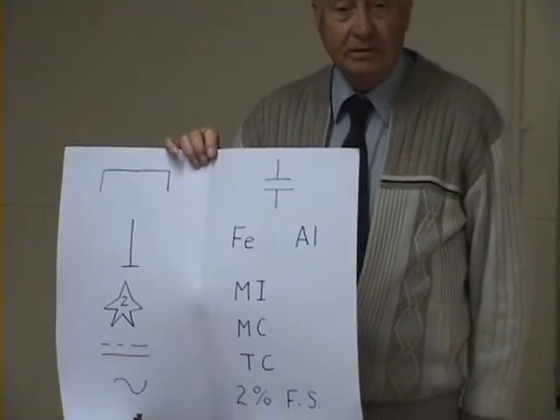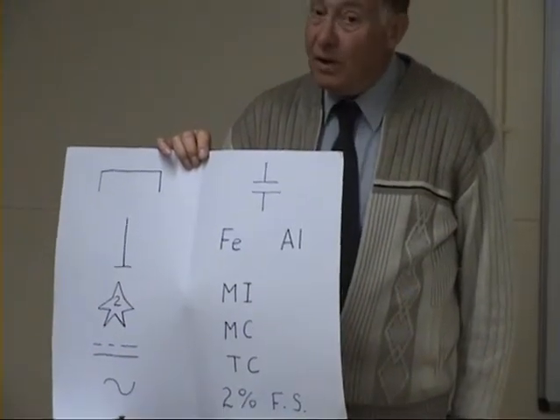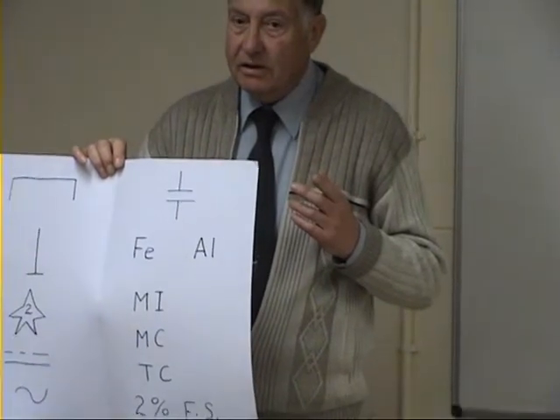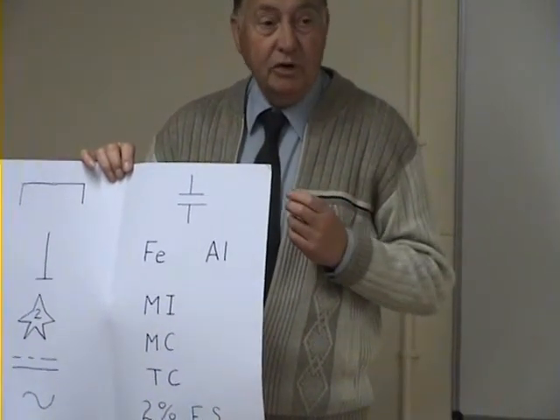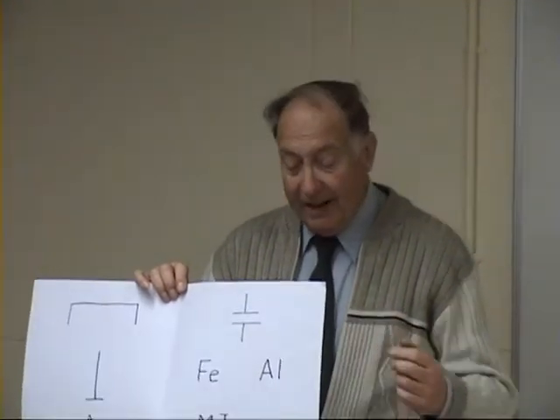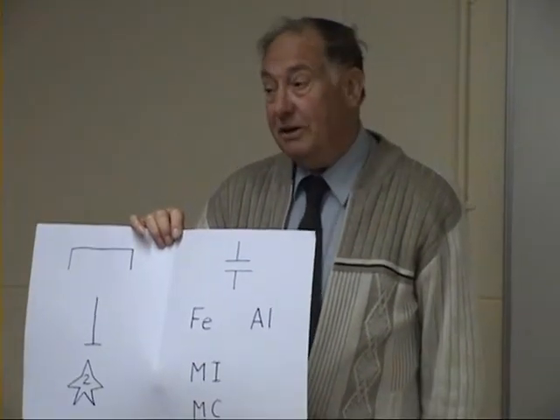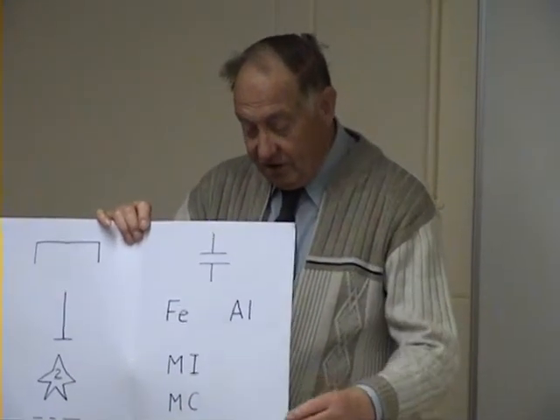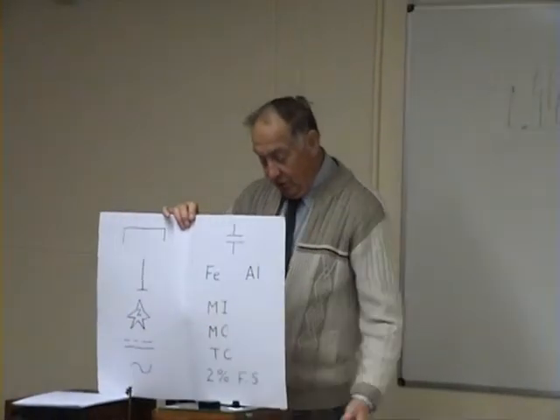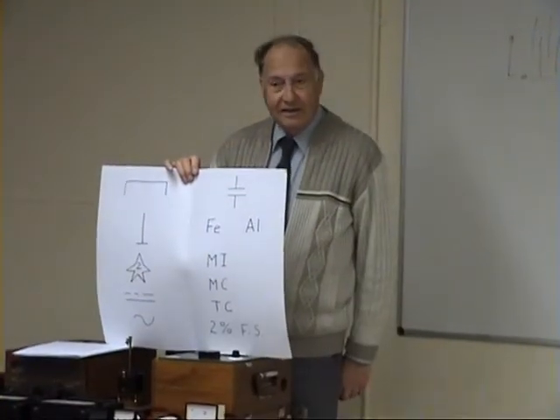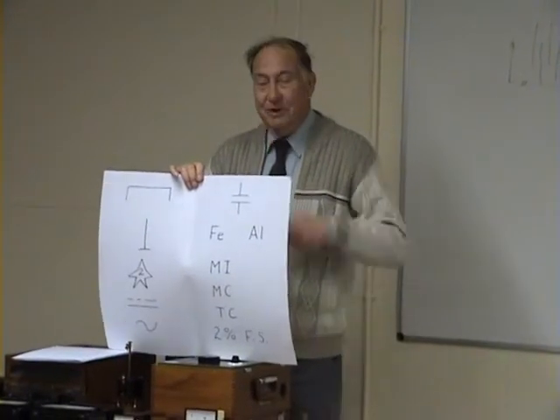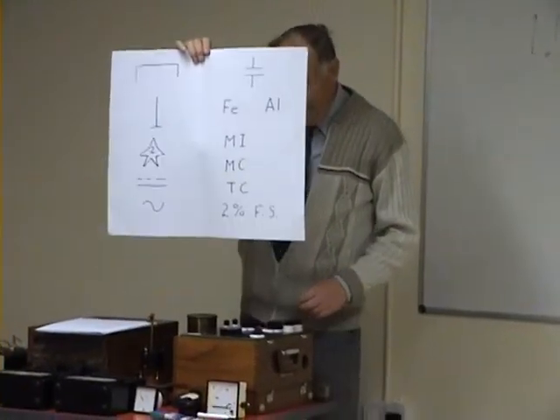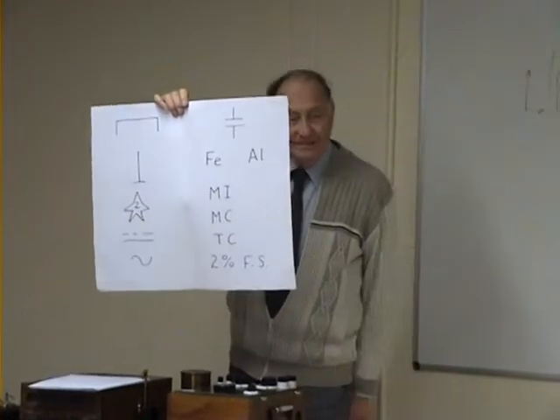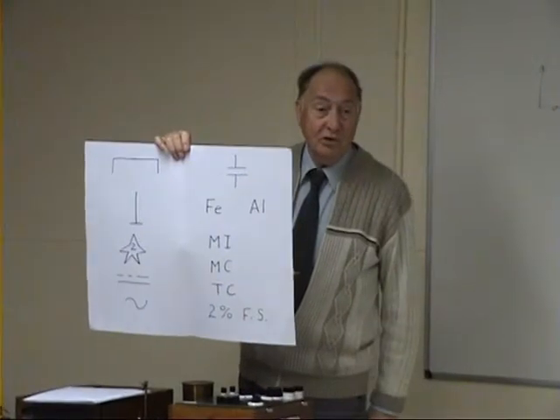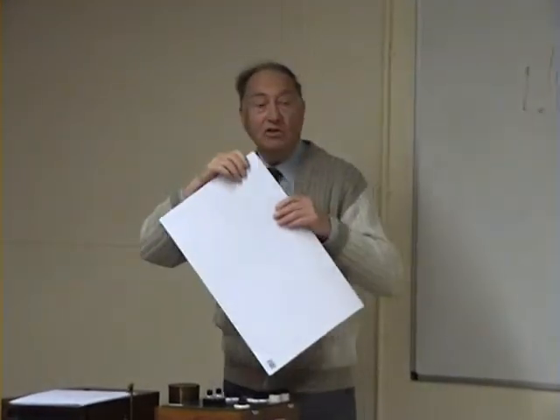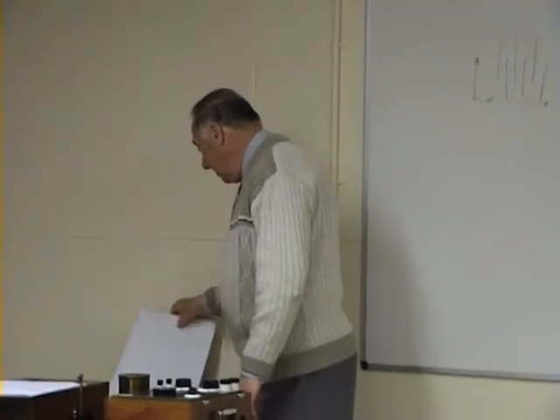FE written on the scale - moving iron? No, not moving iron, nearly. It means it's calibrated for use in an iron or steel panel, and similarly aluminium is calibrated for aluminium. Then you get moving iron, moving coil, TC - thermocouple instrument - and 2% FS, which is the accuracy level, 2% of full scale deflection. There you are, it might give you some idea of what you might be chasing.